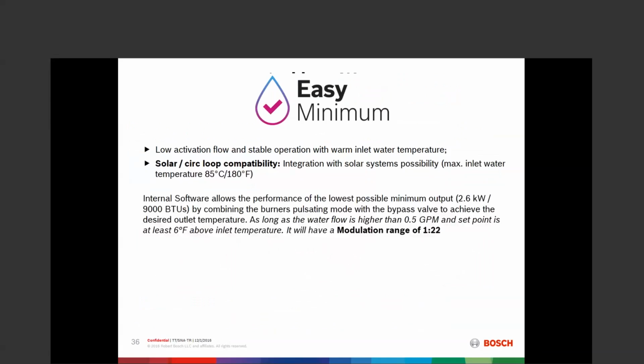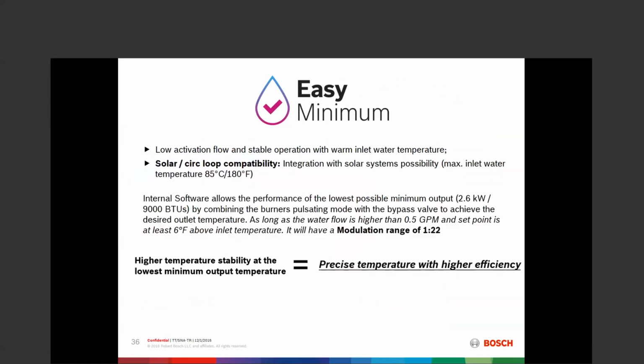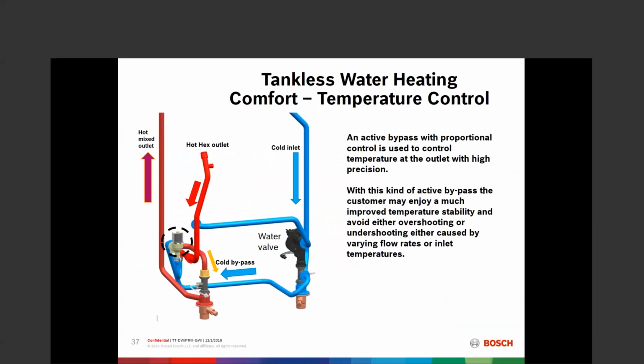Easy minimum is an interesting function for those of you who might live in warm water areas. What it allows the unit to do is effectively set itself up in a managed short cycling, in order to maintain temperature at very, very low flow rates with very warm inlet water temperature. And all of that is using what we call our active bypass. In that idea of a pulsating or short cycling burner, it's overheating the heat exchanger, and then overheating the heat exchanger drops the burner out. So the water flow looks like this. We have our cold coming in. Again, it comes in from the top on the indoor units, comes down to a T.